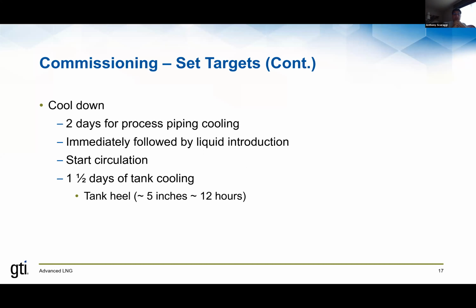For cooling down a tank, 1.5 days about. Once again, these are not hard and fast rules. These are ideas of what these targets look like, and you want to build what's called a heel in the tank, meaning a small amount of liquid in the tank that will keep the whole tank cold. And the typical range for that is you build about 5 inches of liquid into that tank in about 12 hours.